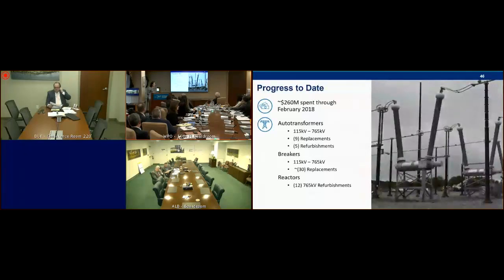So now getting a little more into specifics about TLEM to date. Through February of this year, we've expended approximately $260 million across all projects under the program. This includes replacement of 9 auto transformers and 5 refurbishments, ranging in voltage from 115 to 765, replacement of 30 breakers in that same voltage class, and refurbishment of 12 reactors, both at Massena Substation and at the Marcy Switchyard in central New York.